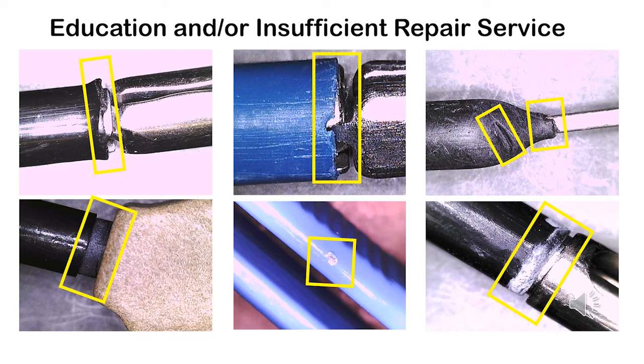The picture on the top right was overlooked because they didn't have the right magnification; they didn't have a microscope, only a desktop magnifier, so they didn't even know the damage was there. In the bottom left, the proximal end was overlooked by the repair service, and the staff didn't know there was even damage where the handle meets the shaft. In the middle bottom, you can see a pinhole in a bipolar forceps that was overlooked, again because of not having the right magnification. The bottom right is old damage. You can see hard water building up where the shaft insulation is backing away from the distal end. This was a lack of education to be able to know that this was actually bad insulation damage.